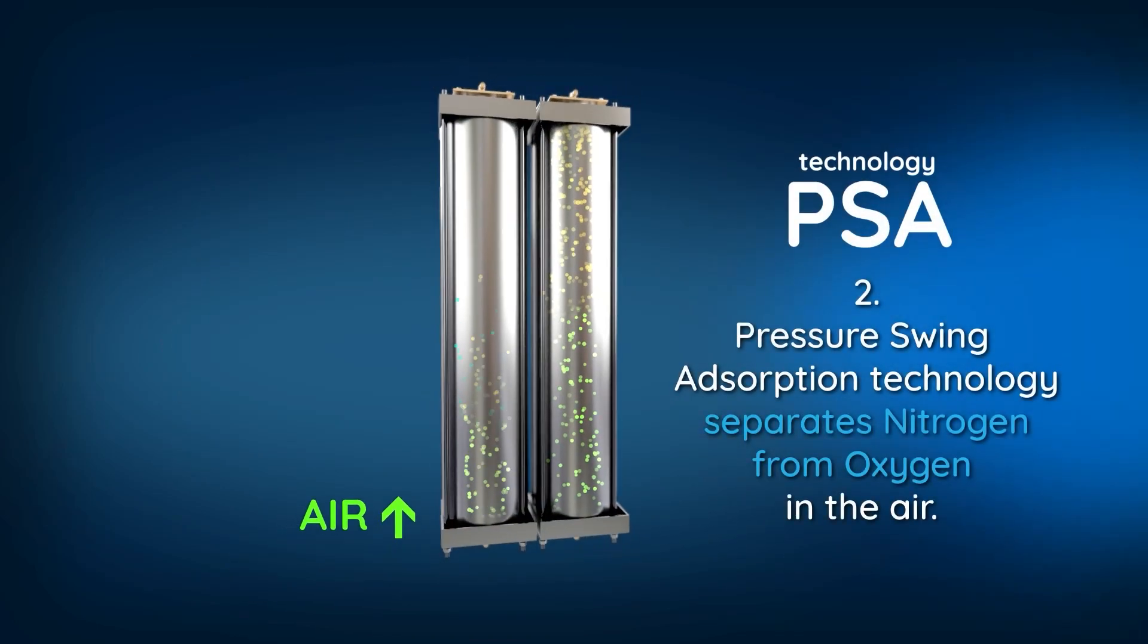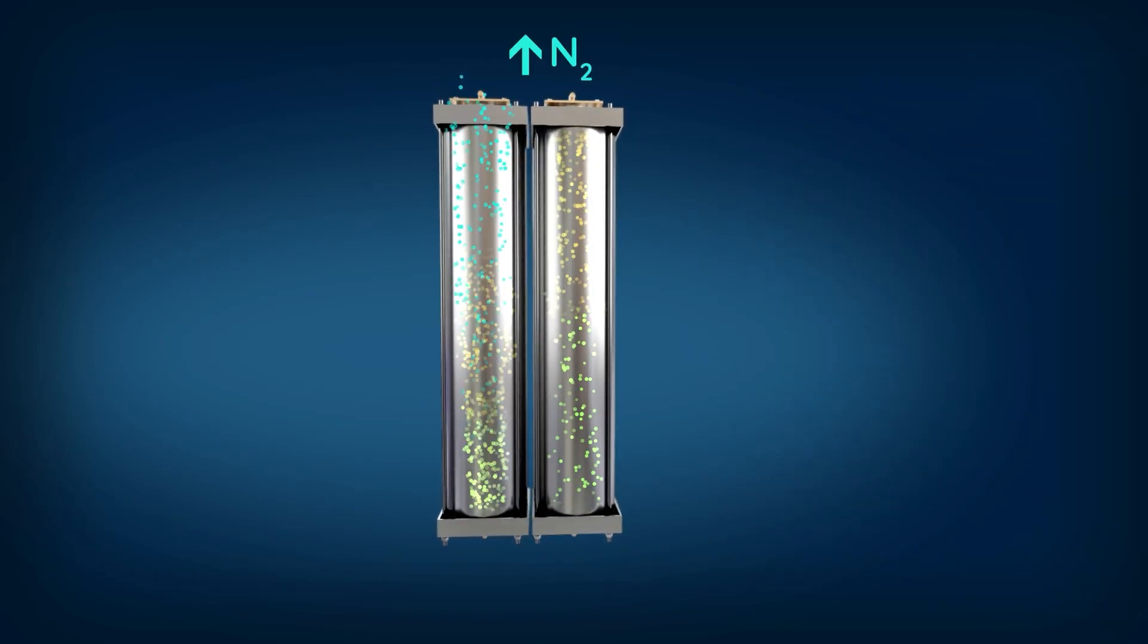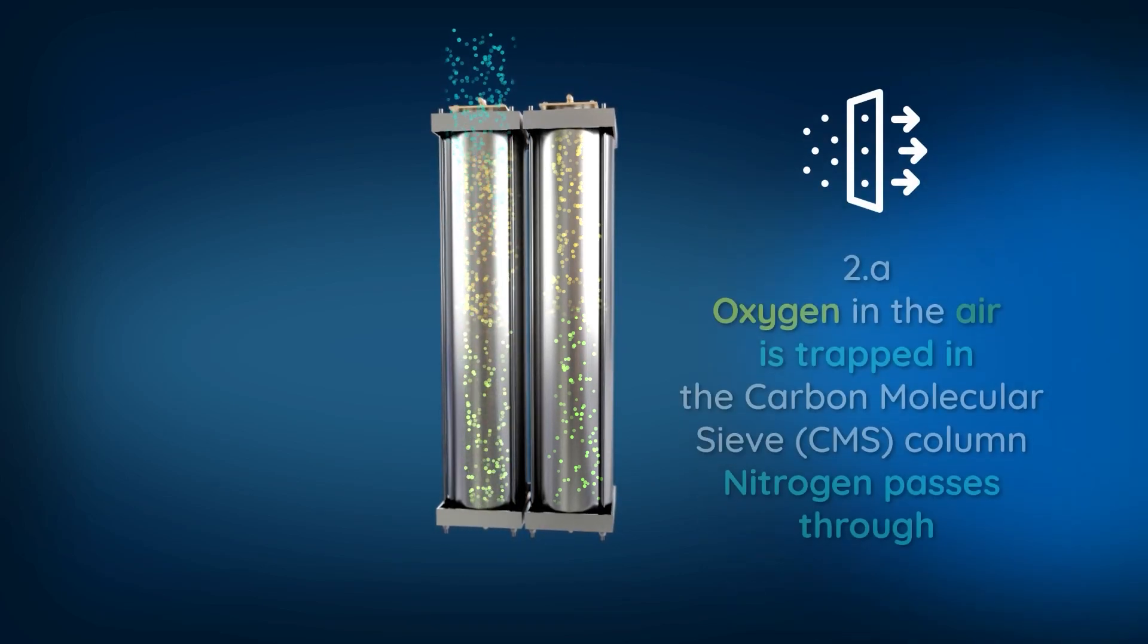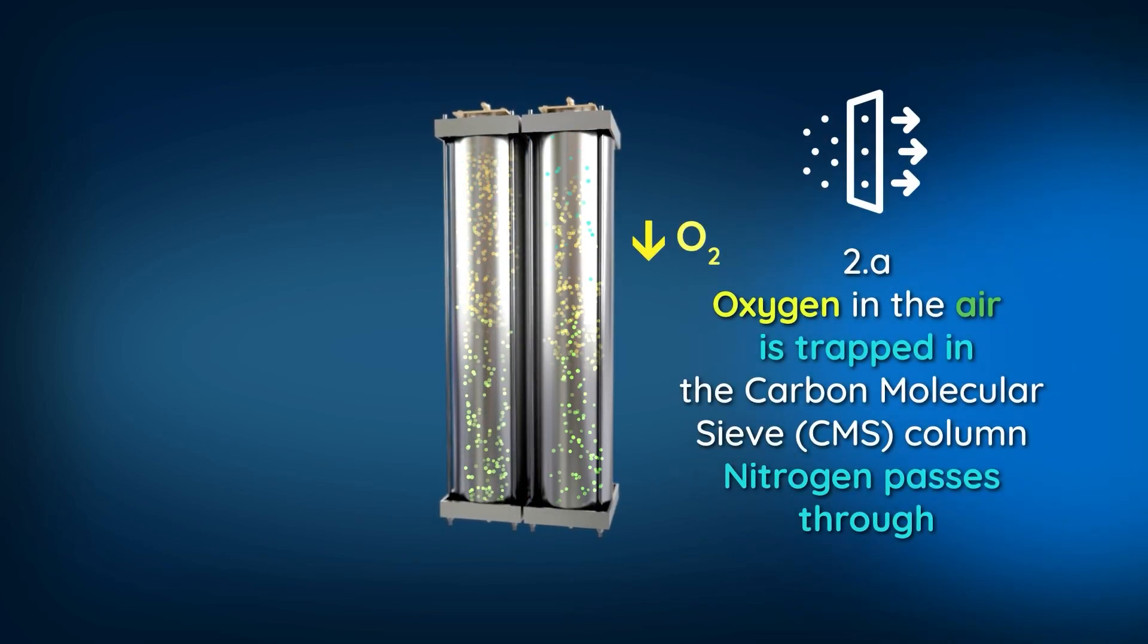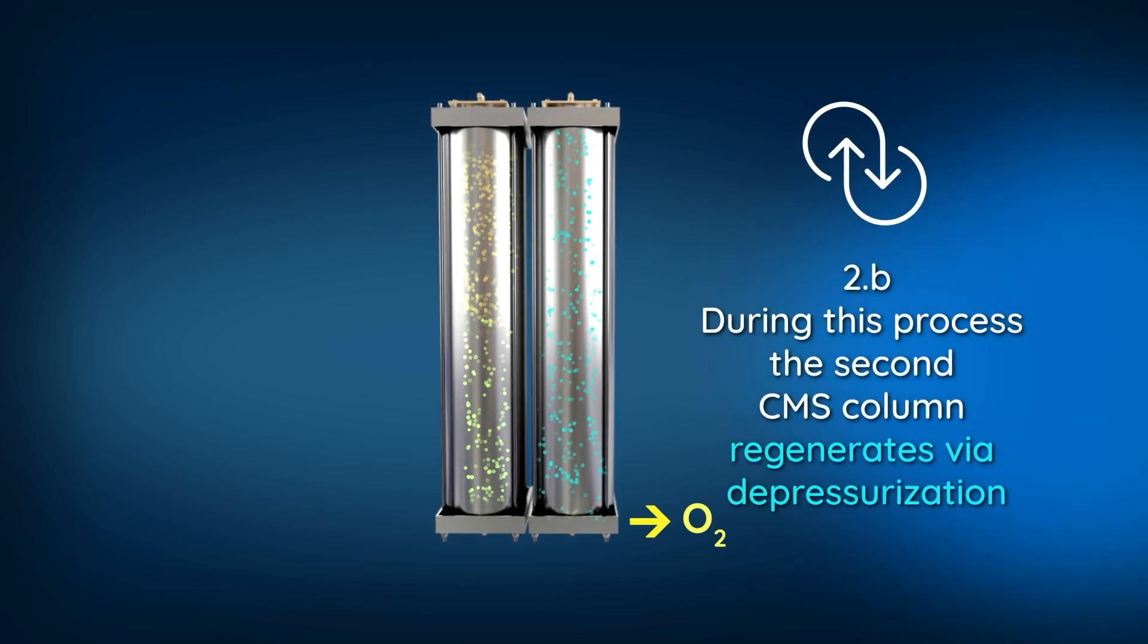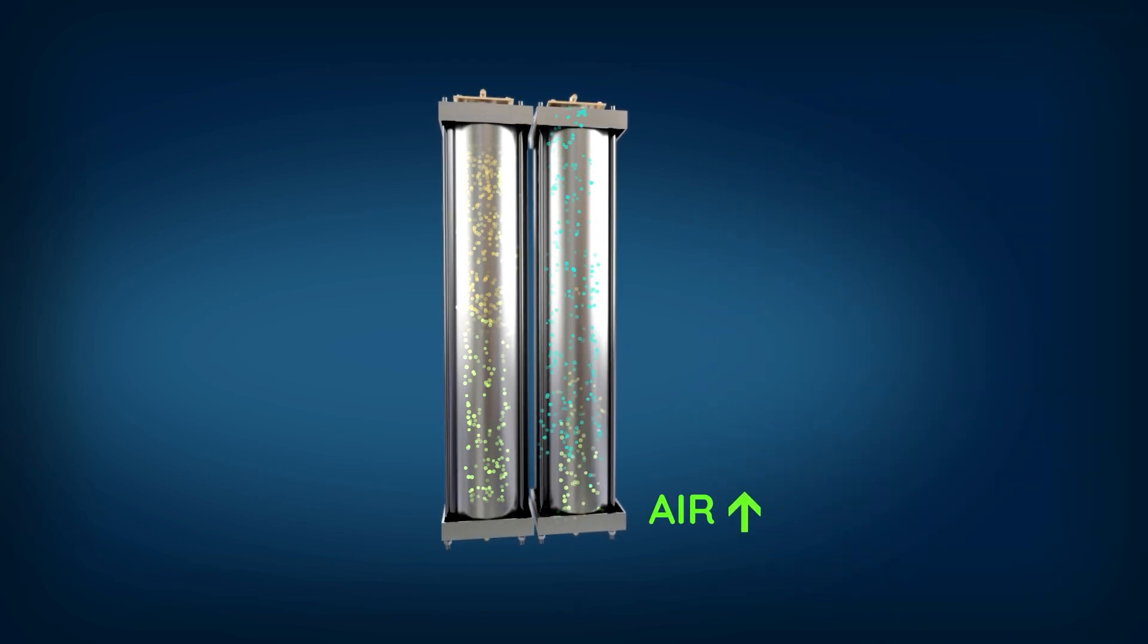Pressure swing adsorption technology separates nitrogen from oxygen in the air. Air passes through a carbon molecular sieve column to separate nitrogen from air. During this process, the second CMS column regenerates via depressurization.